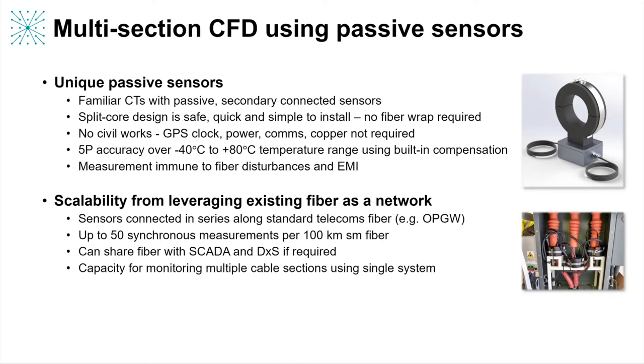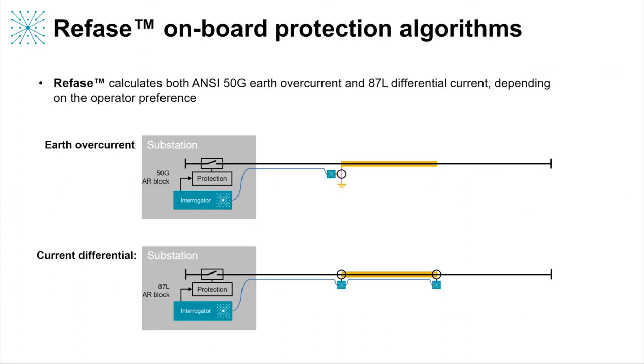Each sensor is compliant with the protection class international standard over the full operating range. Our sensor technology is uniquely scalable among power systems instrumentation — we can perform up to 50 measurements on a single fiber up to a nominal maximum distance of 100 kilometers from the interrogator IED. If there's no spare fiber available in your network, we can actually share fiber bandwidth with communications traffic for SCADA purposes or even with other distributed measurement technologies like DAS or DTS — distributed acoustic or temperature sensing.